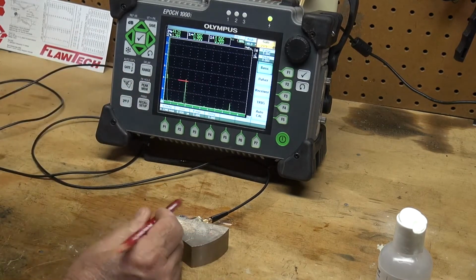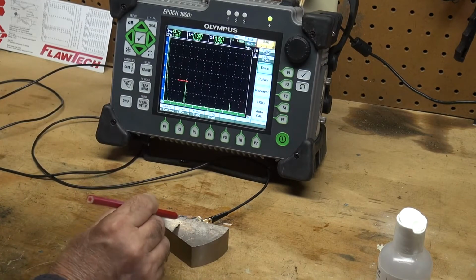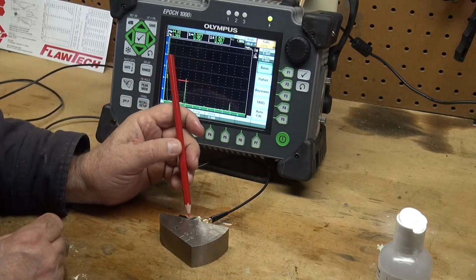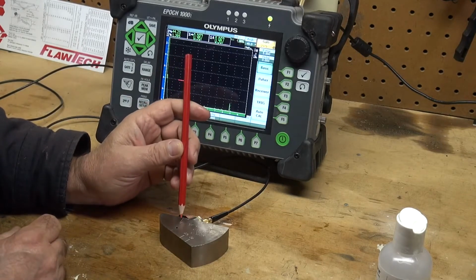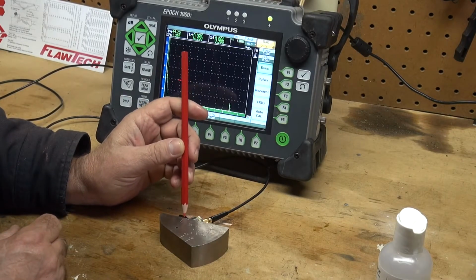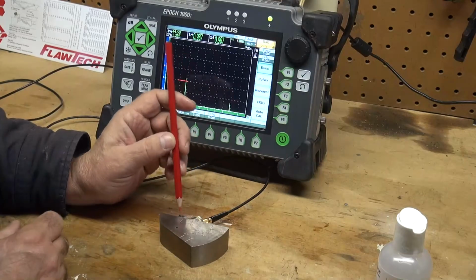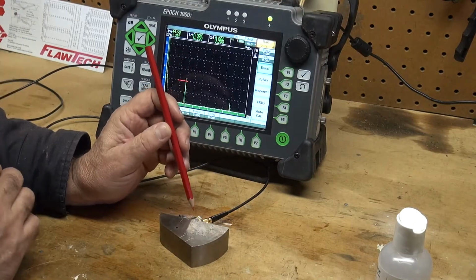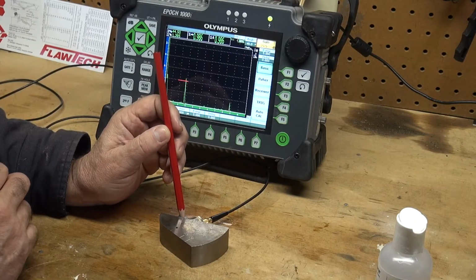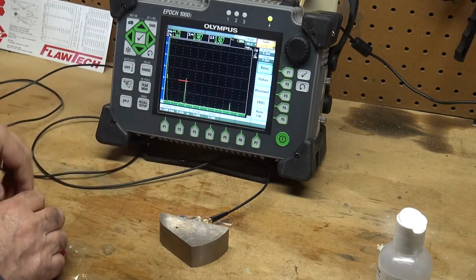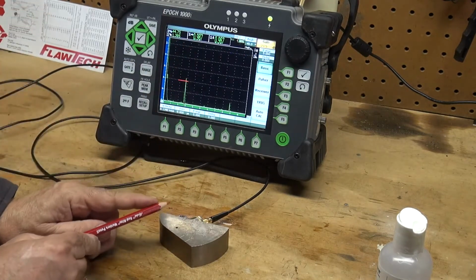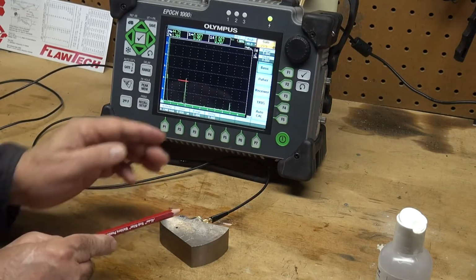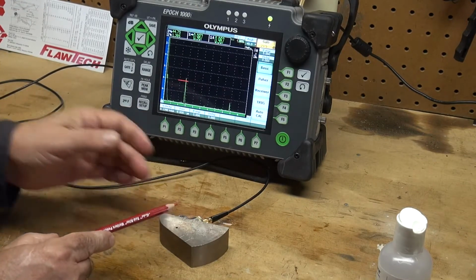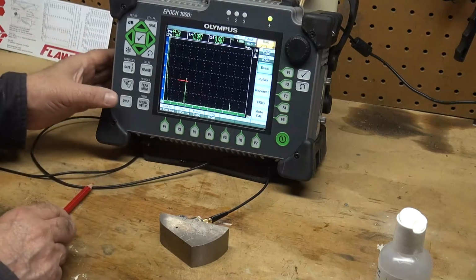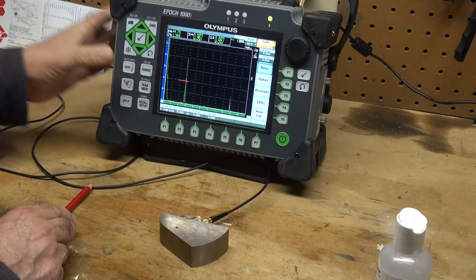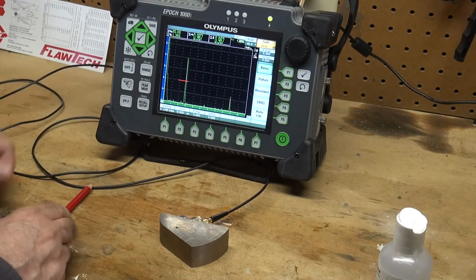So again, this zero marking is the beam index point, and I put a piece of masking tape on my wedge, and I transferred that zero marking to my wedge. That's your beam index point. All your measurements are taken from that beam index point. And the beam index point is where the majority of the energy coming out and receiving back to that transducer is.